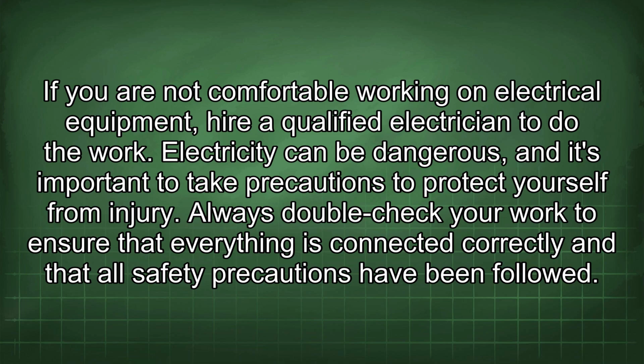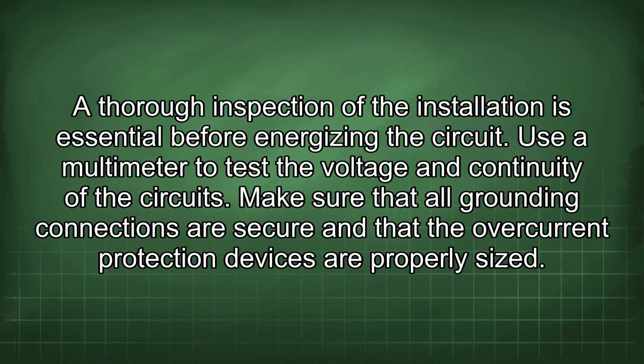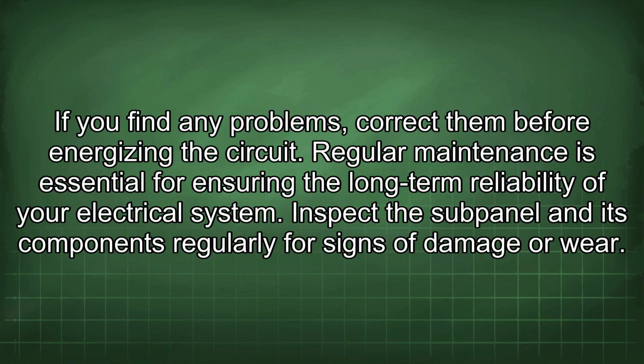Always double-check your work to ensure that everything is connected correctly and that all safety precautions have been followed. A thorough inspection of the installation is essential before energizing the circuit. Use a multimeter to test the voltage and continuity of the circuits. Make sure that all grounding connections are secure and that the overcurrent protection devices are properly sized. If you find any problems, correct them before energizing the circuit.